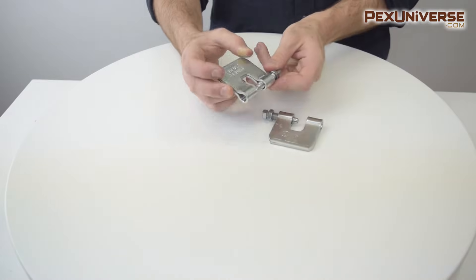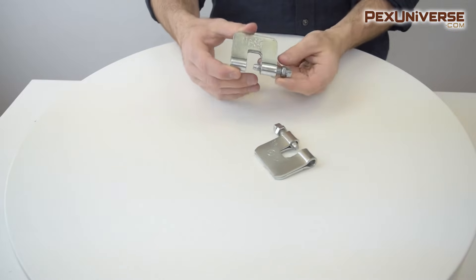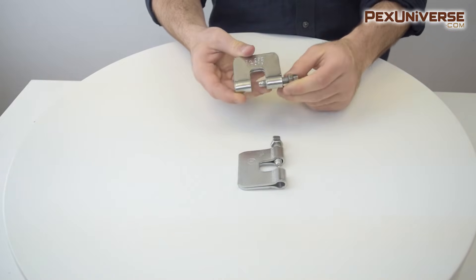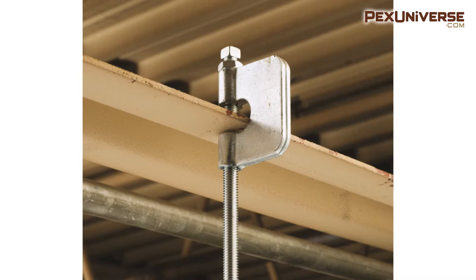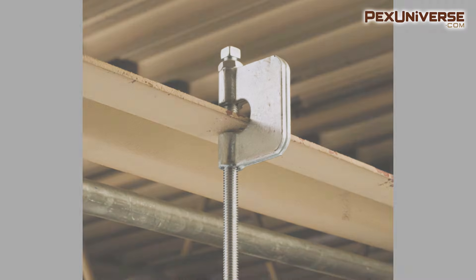Steel C clamps are designed for attaching a hanger rod to the bottom flange of an I beam and the hanger rod should make contact with the beam to ensure full engagement. These are made of low carbon steel and can hold a max load of 400 pounds. They come in plain or galvanized steel.